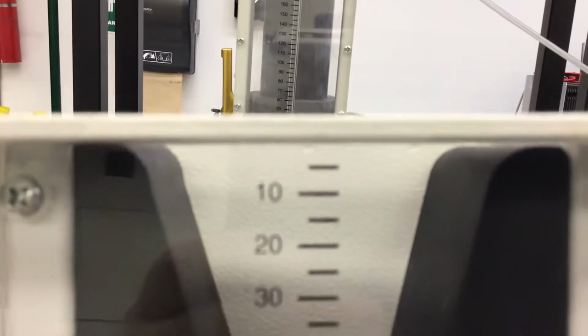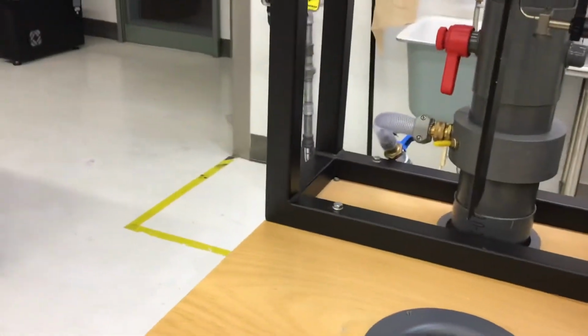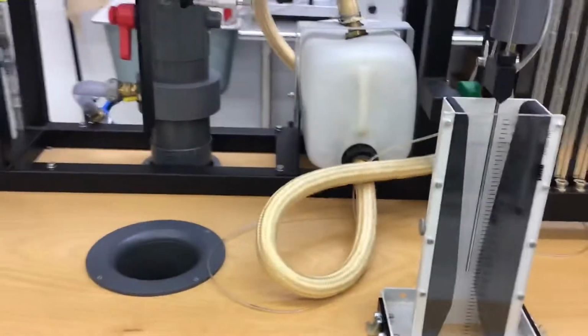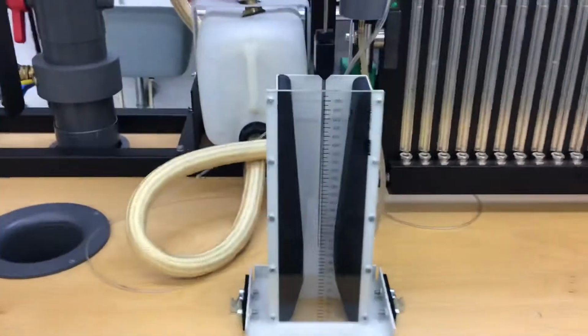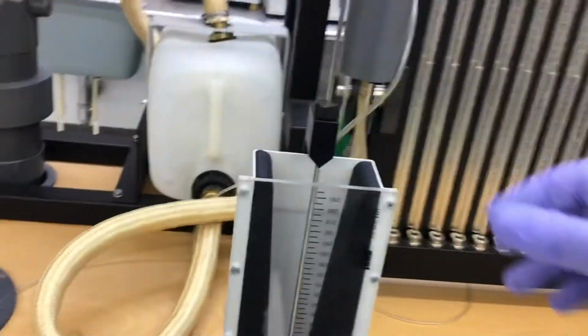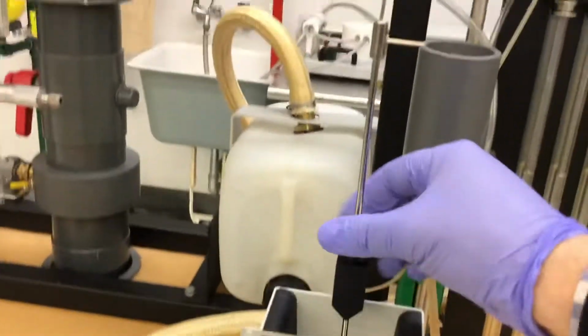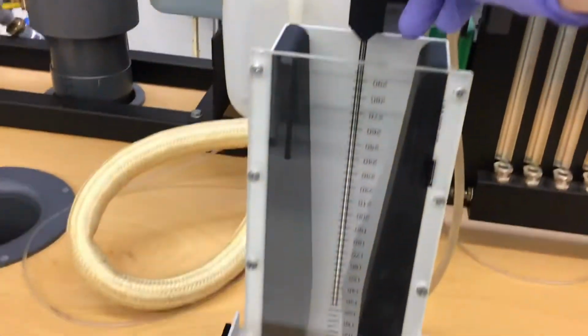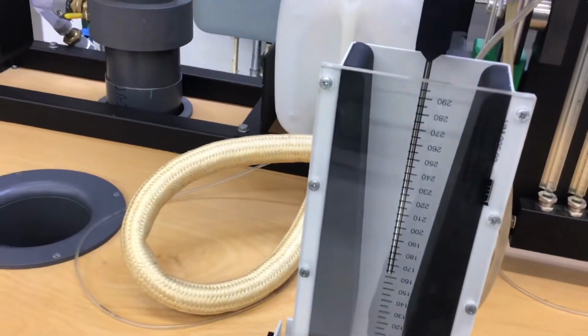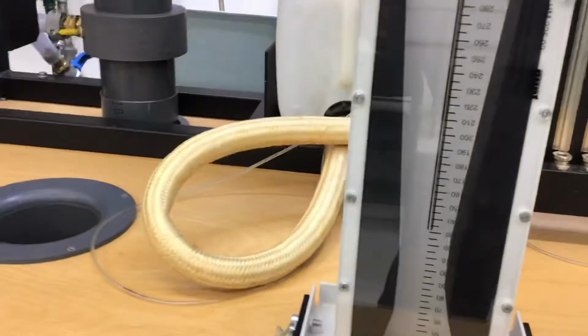So you can see the cross-section area starts big, gets smaller, constant from 60 to 100, and then gets bigger again as you go downstream of the flow direction. So with this, you can keep measuring at different locations by changing the location of the pitot tube itself. You can untie this and move the pitot tube up and down to get different measurement locations.